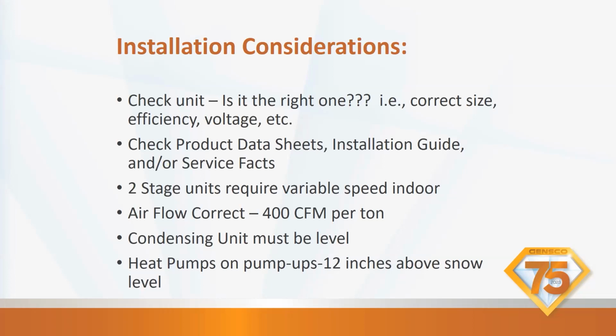Two-stage units require variable speed indoor motors. Don't forget that. Is the airflow correct? Can you get 400 CFMs per ton out of the indoor unit that you're proposing or that's existing? The condensing unit has to be level. And don't forget that heat pumps need to be on pump ups. They need to be 12 inches above snow level. We have those racks that work for mini splits. We also have those for side discharge units.